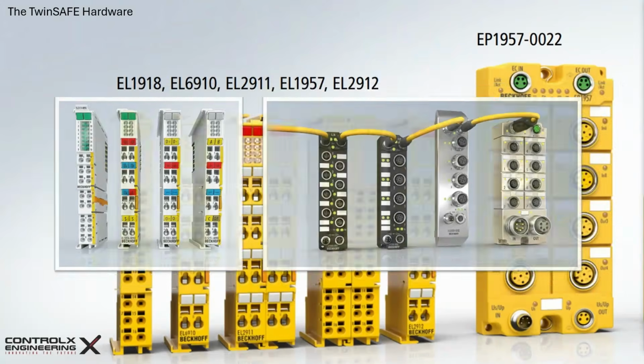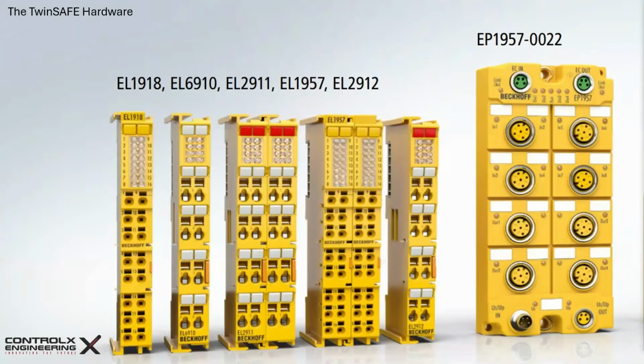components and the black and stainless steel IP67 and IP69K boxes for field I/O. They are fast, reliable, and great for standard control. But when it comes to human life and high-risk machinery, standard I/O isn't enough. Enter the yellow terminals. The most obvious difference is the color. Yellow indicates compliance with SIL 3 and PLE standards.